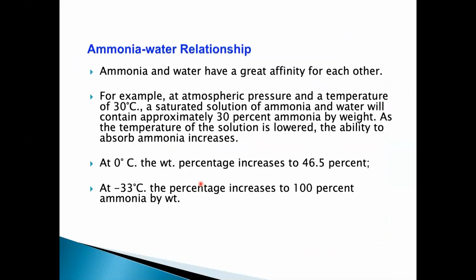The second part, I was trying to tell you about water. Water has a very high affinity with ammonia. So when it mixes, anhydrous ammonia becomes aqua ammonia. In the refrigeration system, we need 99.95% pure ammonia. But if water is there, the ammonia is no longer anhydrous. So what it actually means is that if our temperature is 30 degrees, 30% ammonia can mix into water. If it is 0 degrees, it can be 46%, and at -30, it can be 100%.